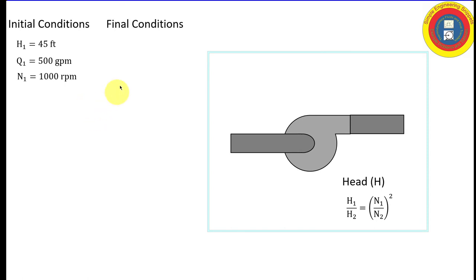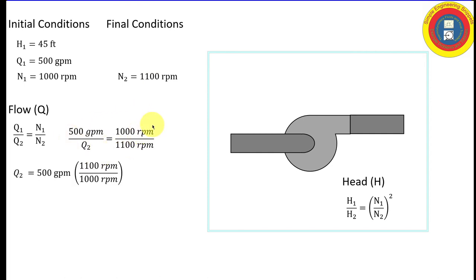We're given the initial conditions. The final conditions are going to be noted with a subscript two. We have the final pump speed, 1100 RPM. So let's start with flow. Using the affinity law, we can quickly solve for the final flow, which increased by 10% as we expect it to 550 gallons per minute.